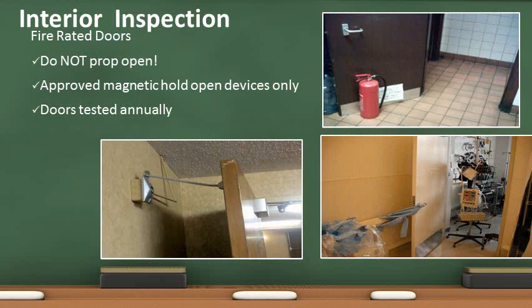Fire doors shall be inspected annually at a minimum and repaired or replaced whenever damaged. Fire doors must self-close and latch and may not be propped open. All photos on the right show good examples of defeating the purpose of a fire-rated assembly.